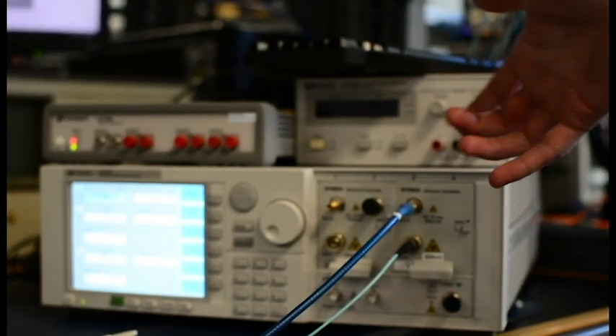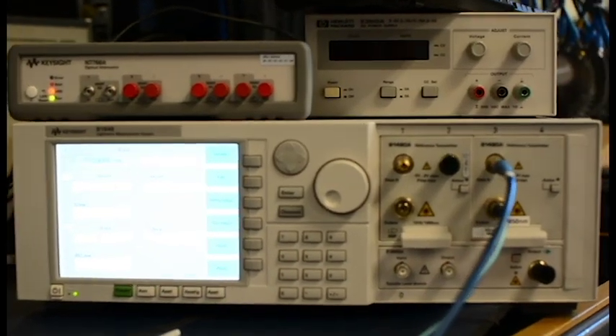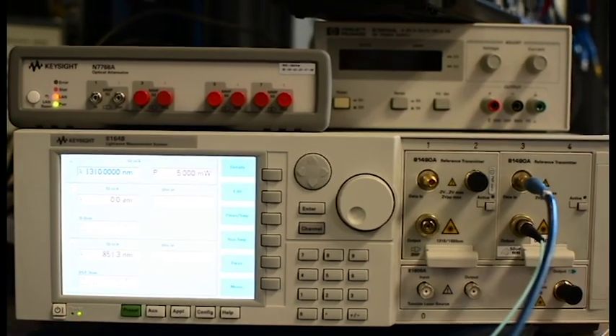So this will take the electrical signal coming out of the BERT, convert it to optical so we can test modules, both transmitter and receiver. So that's the tour of the equipment.